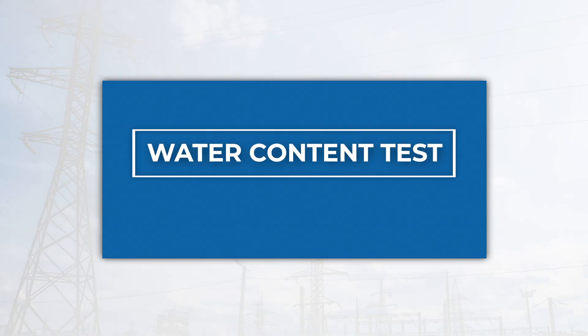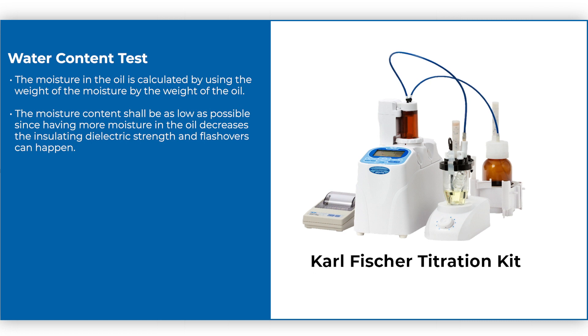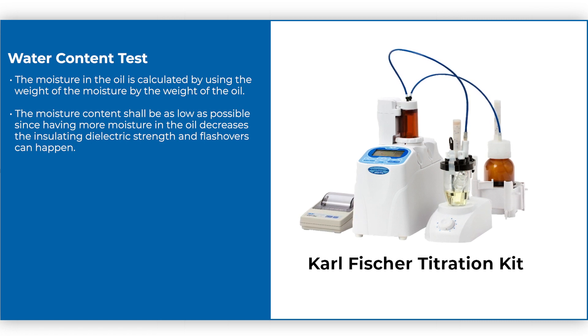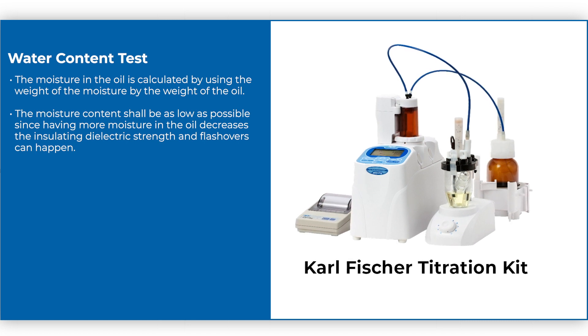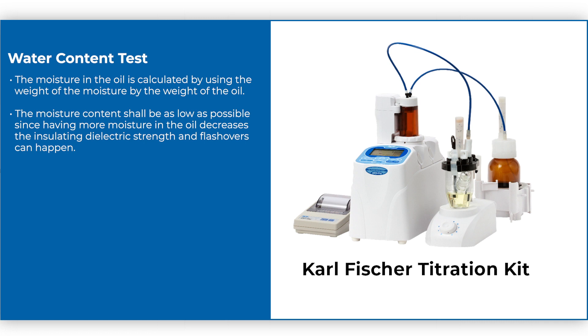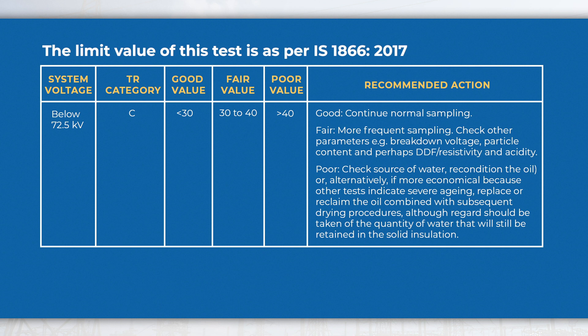Water content test: The moisture in the oil is calculated by using the weight of the moisture by the weight of the oil. The moisture content shall be as low as possible, since having more moisture in the oil decreases the insulating dielectric strength and flashovers can happen. The limit value of this test is as per IS 1866:2017, given in the table.